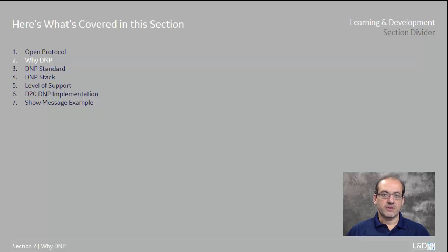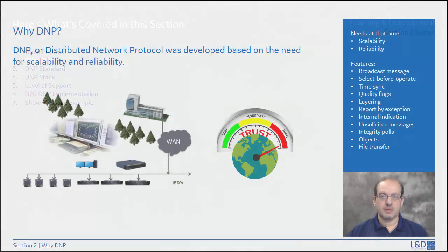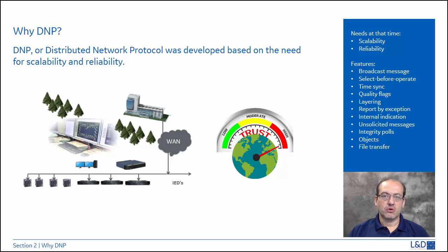With the shared protocol being available and many others, the question is, why DNP? Why do we use DNP? DNP was developed as a result of all the knowledge that Westronic, or what used to be known as Westronic and today is GE, gathered in the world of SCADA and automation. So there are a lot of benefits that exist in DNP. Select before operate, broadcasting of messages, quality information that's constantly exchanged between the device and the master, or the device and the client, informing of all the different information about the device.